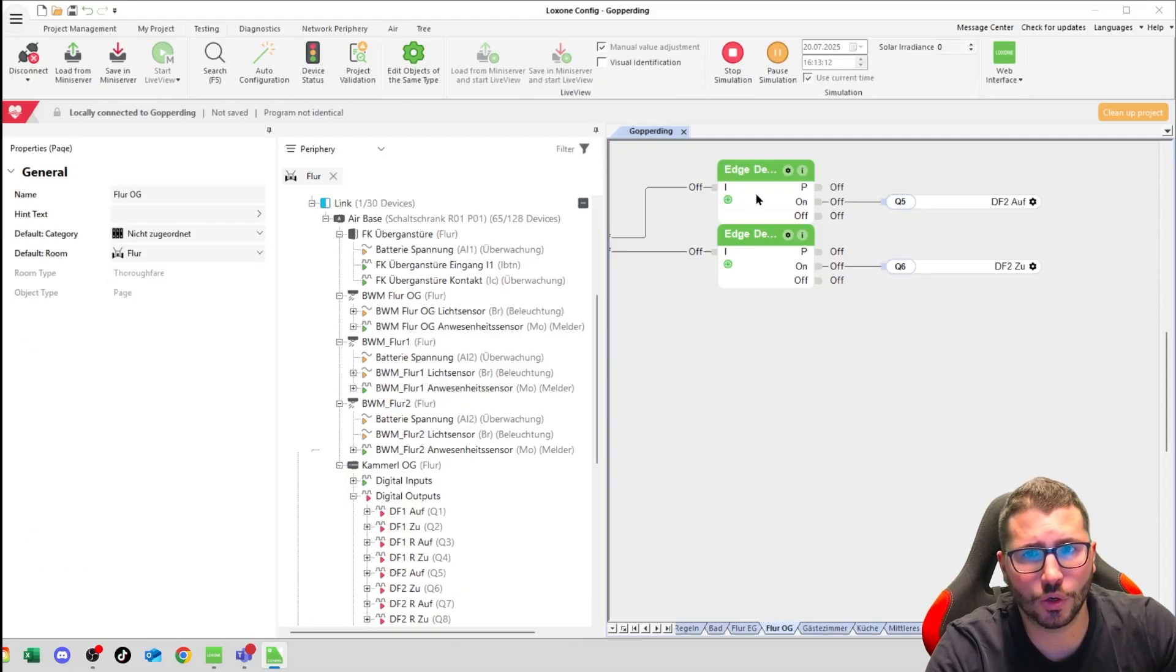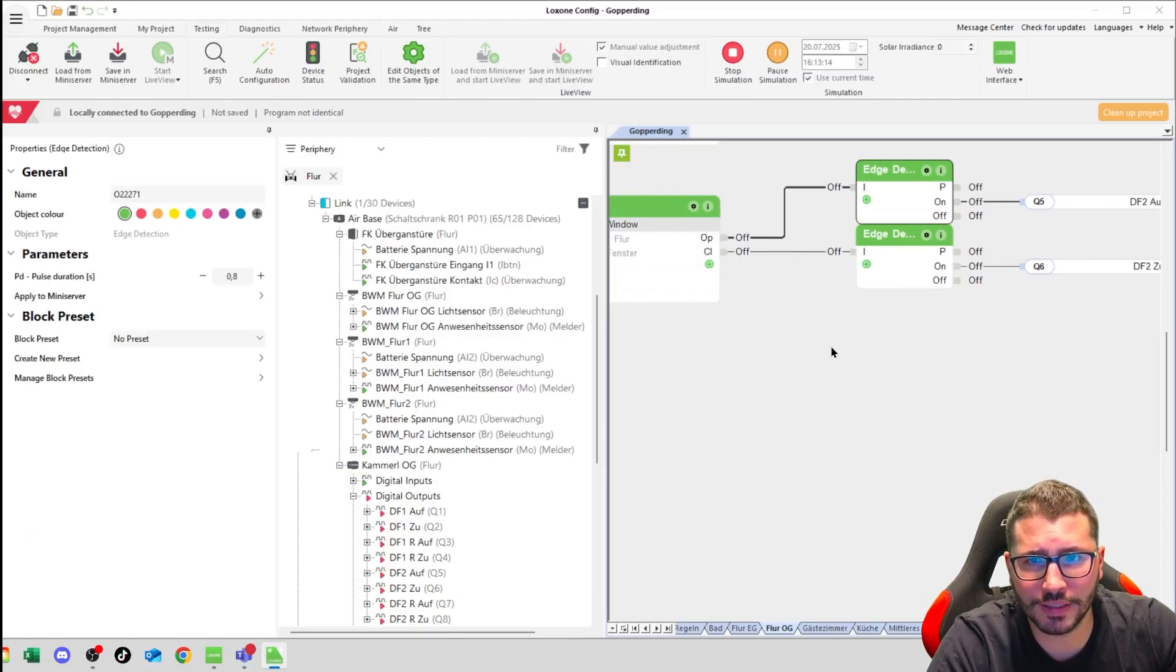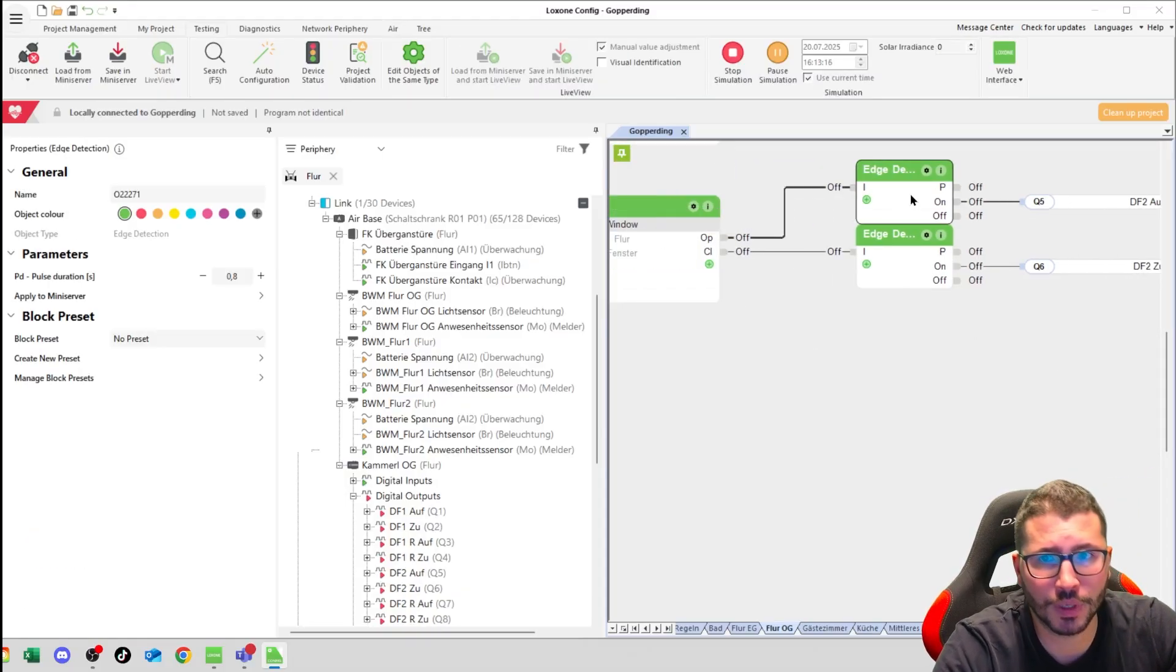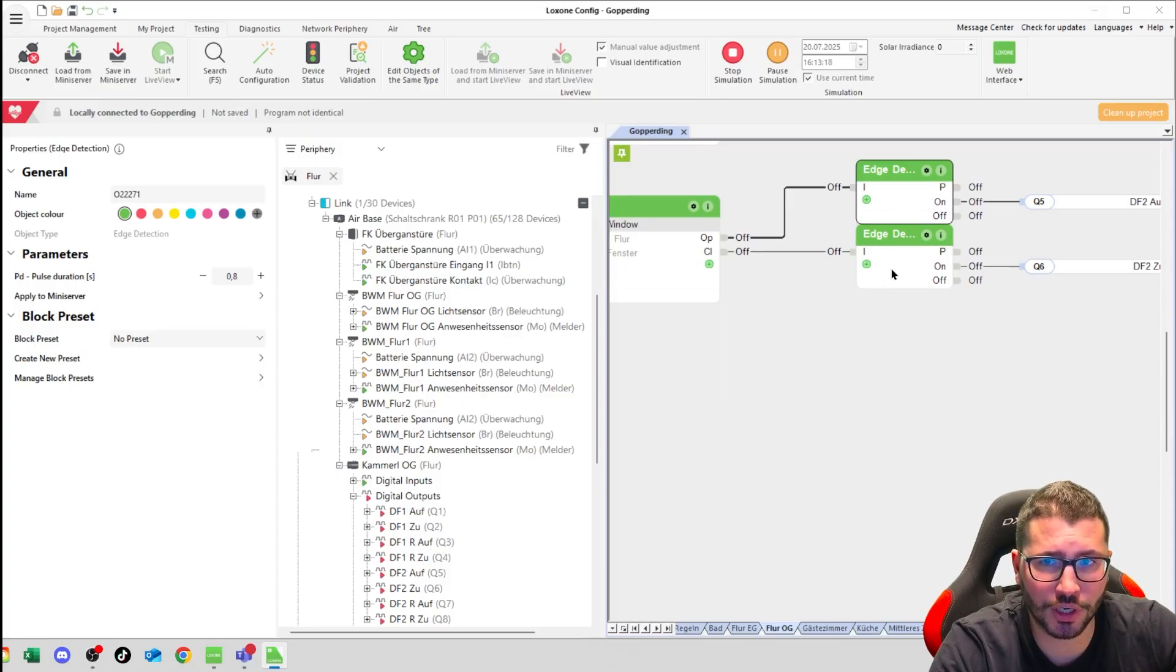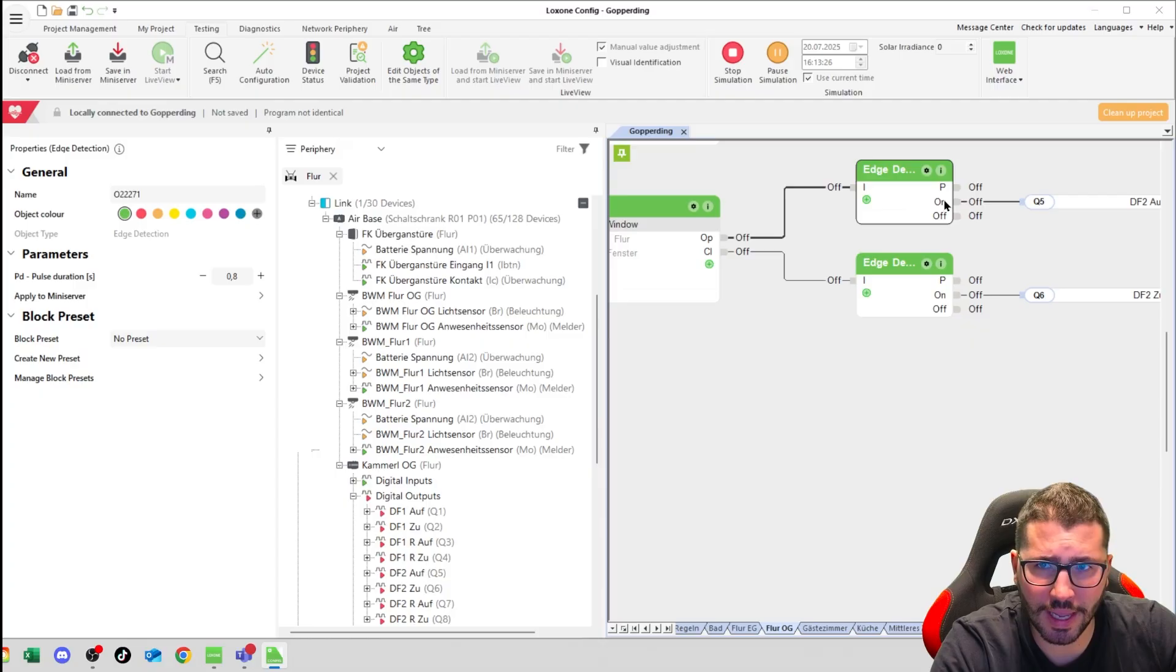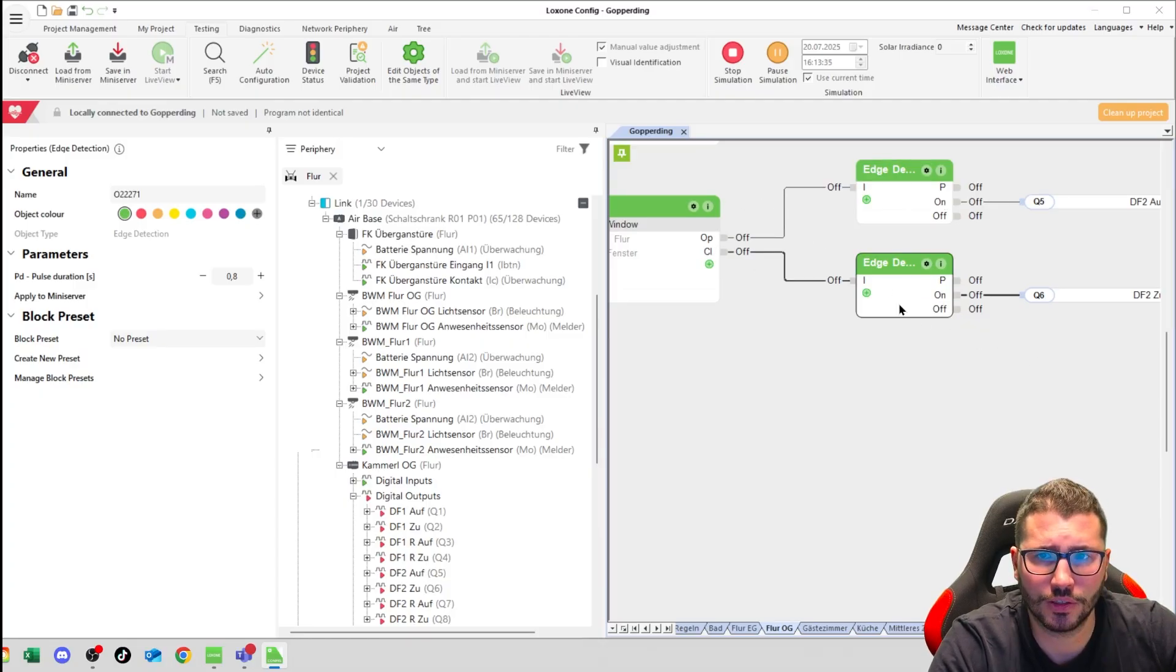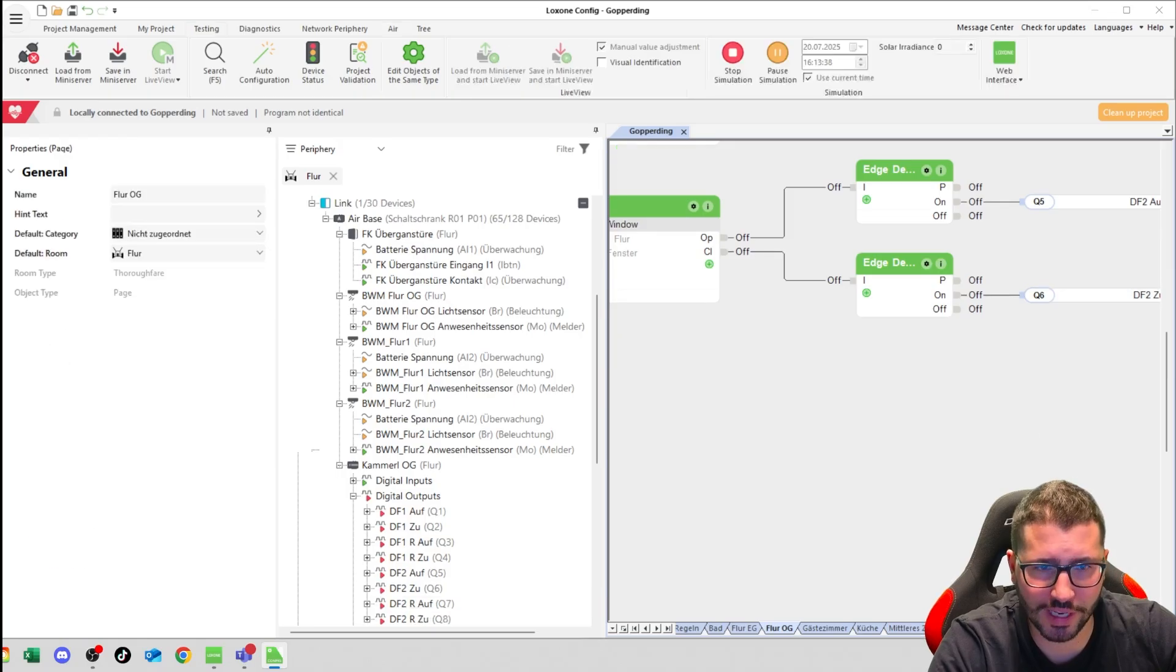So I transform this permanent signal here. I could use a monoflop, but I used an edge detection because it's more reliable in this scenario. I go on to the on edge here and the on edge on the close to have a quick pulse here on these relays.